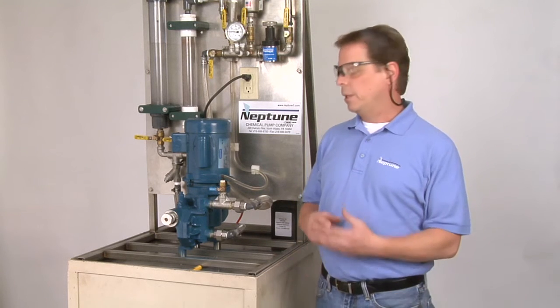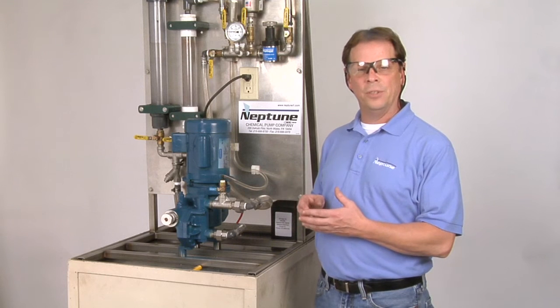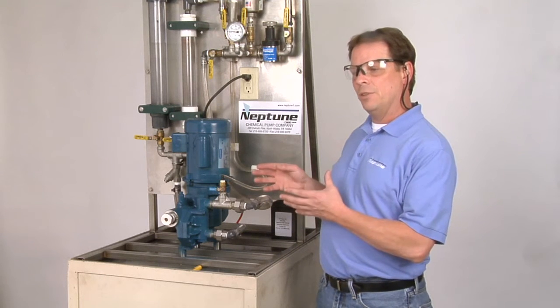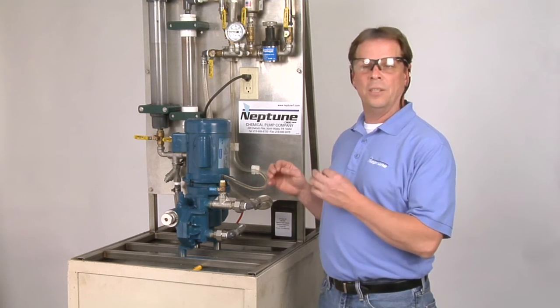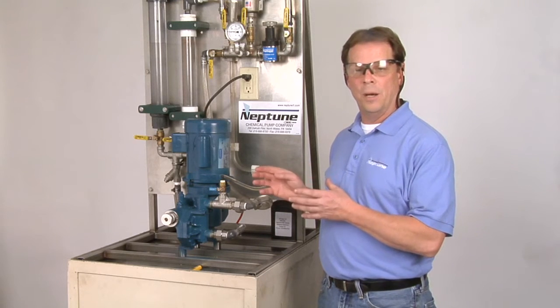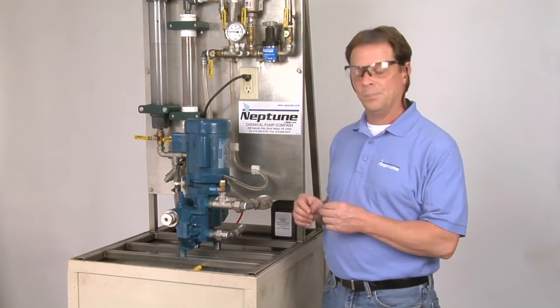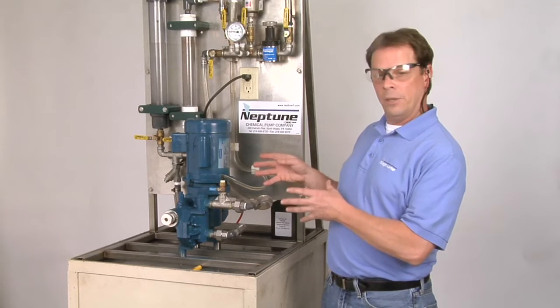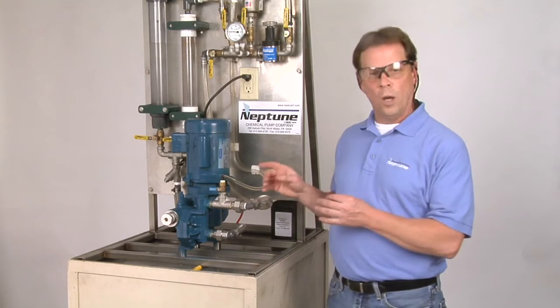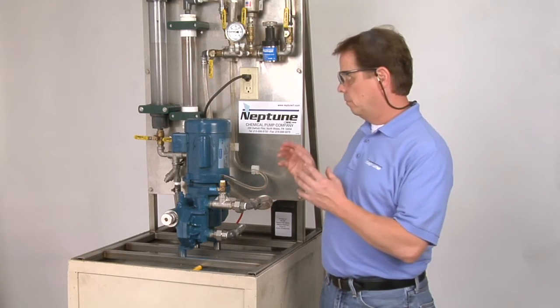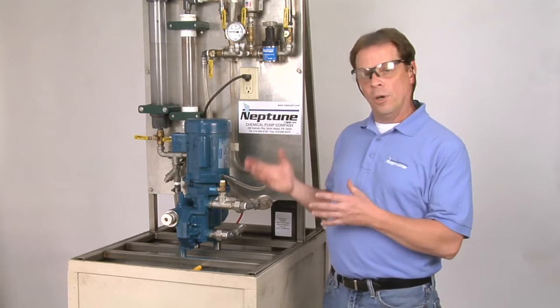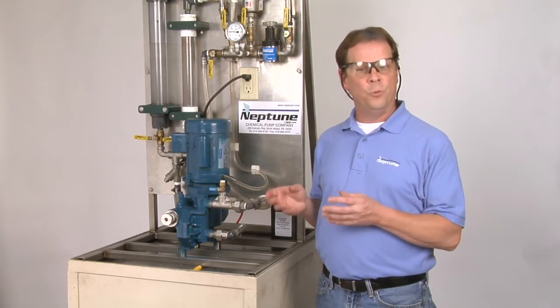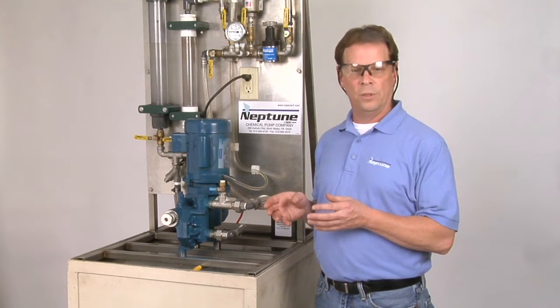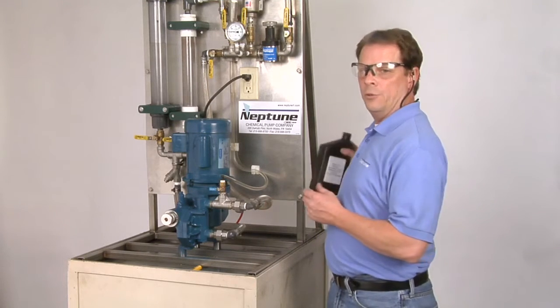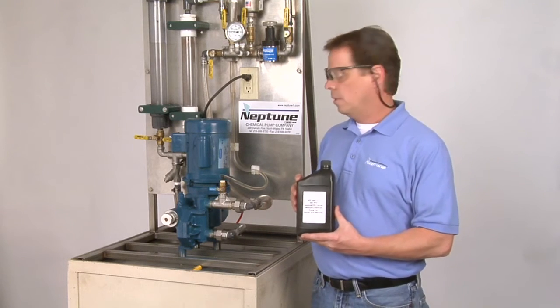Today we're going to be doing the startup procedure on our 500 series pump. The 500 series pump is similar to the 560, 600, and 6000 series pump. Basically the same procedure. So today, this particular pump uses 1 quart of oil in the gearbox. There are other models that might take 2, 3, or even 4 quarts of oil. Oil is critical when it comes to these pumps.